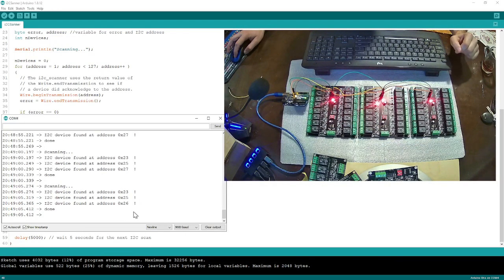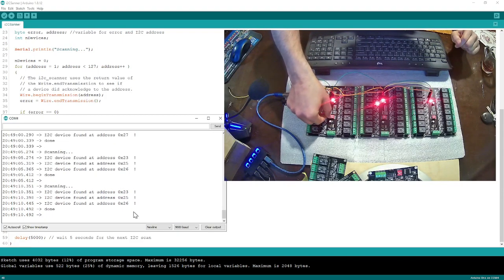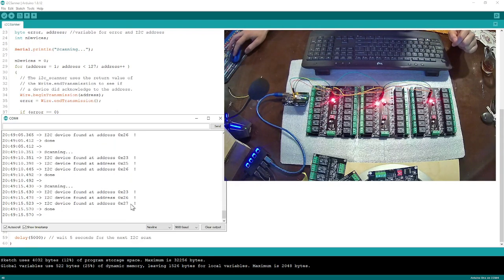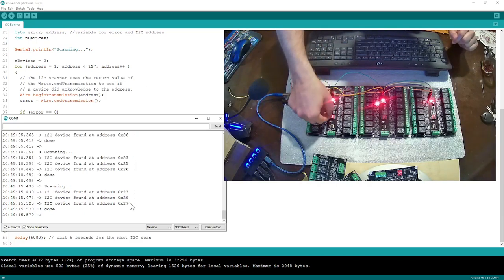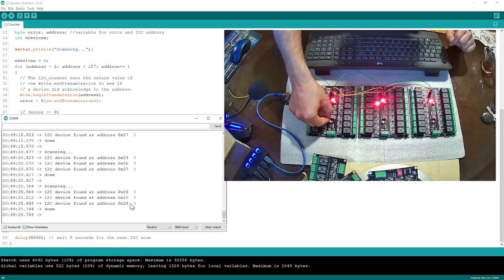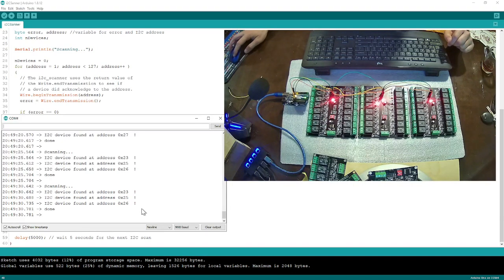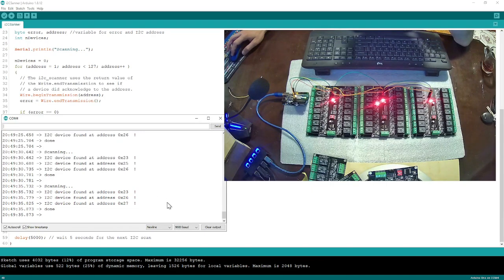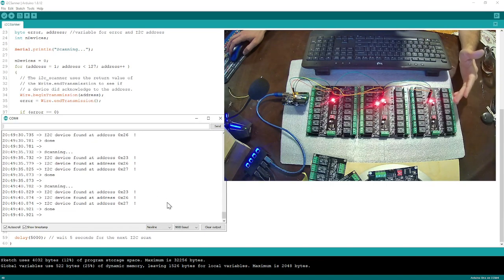Now 26 again. Let me do the same thing on the middle board — switch one is down, I'll flip it up. Now, this is the middle one, so its address is 25. If I flip it up, 25 is going to change to 26. Okay, this is the second way to identify which board has which address.